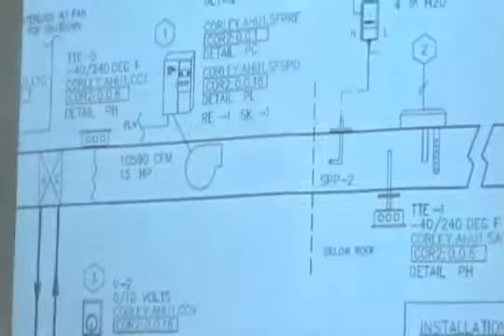Starting with this air handler on these little sheets that I handed out. These will be some similar things that you saw on the other air handler. We're just going to change the rear end of the air handler, what would be up here on the picture. Starting out here on the end, this is the supply air. This is our supply static pressure sensor. We're monitoring the static pressure of this device right here. And like you said last time, the actual sensor itself may be installed at our panel at the air handler, and then tubing run out to some spot in the ductwork. And you'll see in this sequence of operation a little different scenario on how they're doing that one.